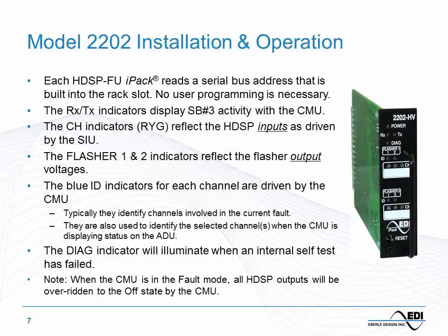There's not much to do to install the load switch or flasher — no programming. You plug it in and it knows its serial bus address because it's hardwired into the connector pins. Depending on the position in the rack the card gets plugged into, it adopts that address and starts communicating to the CMU. The indicators on the front provide red, yellow, green indication of the input to the load switch, RXTX indicating serial bus 3 activity, blue LEDs for flasher output voltages when in flasher mode, and ID indicators for troubleshooting.